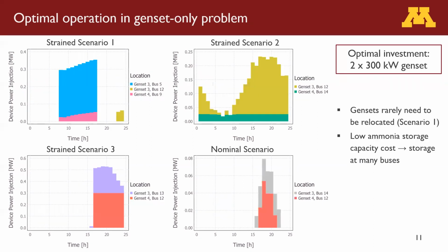In the genset-only problem, we see that the optimal investment is 2 300 kilowatt gensets. We can also see that in these 4 scenarios, the gensets very rarely need to relocate. The only time a genset relocates in any scenario is when genset 3 goes from bus 5 to bus 12 in scenario 1.